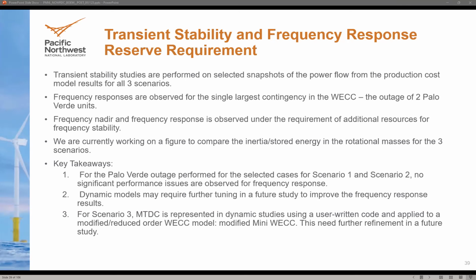For transient stability and frequency response studies, the primary reason we headed this way was to make sure that after all the analysis through the production cost model and contingency analysis, looking at AC feasibility, we also want to make sure with respect to dynamics the system is stable, and that any major disturbance affecting the Western grid, with so much renewables and offshore wind, especially for the 2030 plus cases, doesn't cause the HVDC backbone to have a significant impact on system frequency stability.